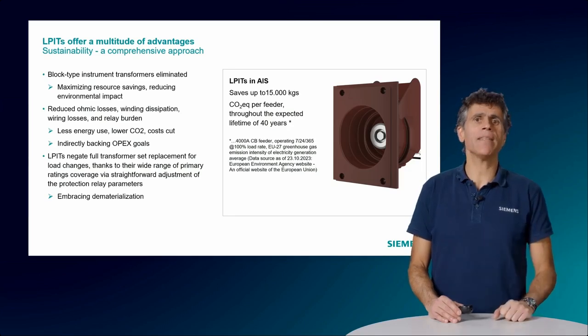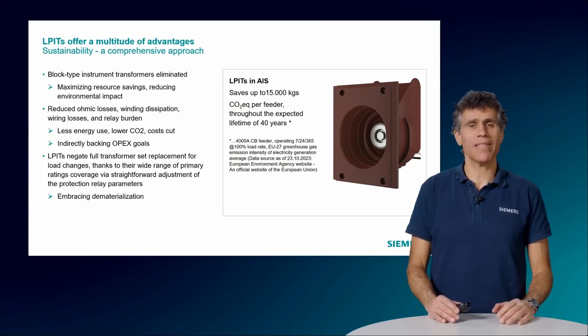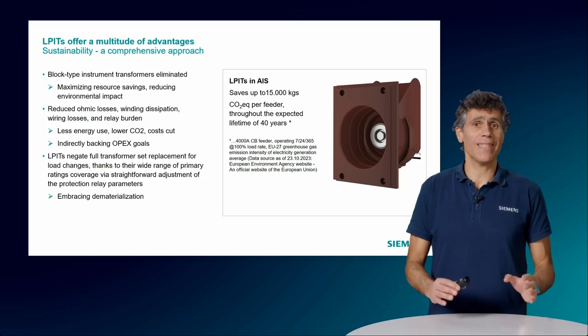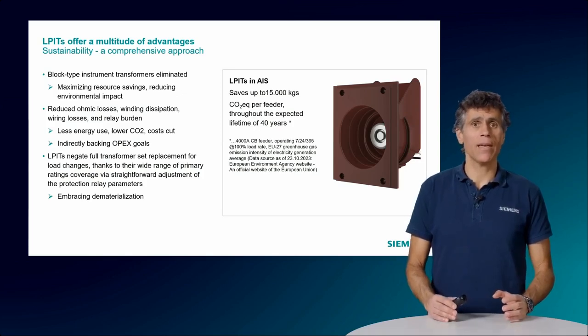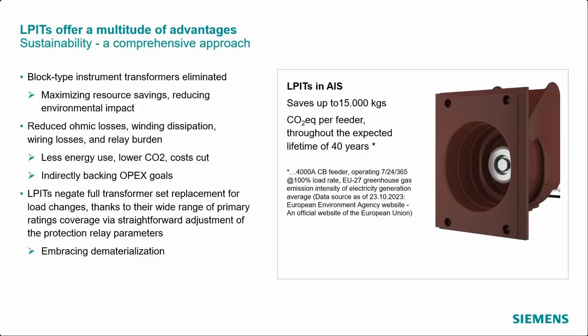First, LPITs are compact and efficient, providing both voltage and current measurements in a single device. You will remember when we talked about the block transformers that we need separate devices for voltage and for current. If you consider that transformers are usually needed in the 3 phases, we need only 3 small LPITs compared to the 6 big block transformers. The LPITs consist of a Rogowski coil, which is an air coil, and doesn't require a ferromagnetic core for the current measurement. Its output in voltage is in the range of millivolts.